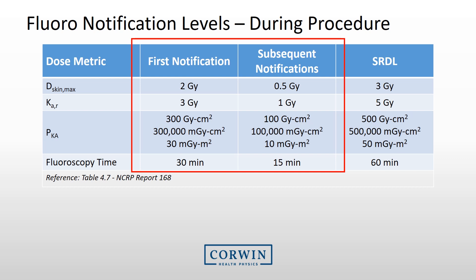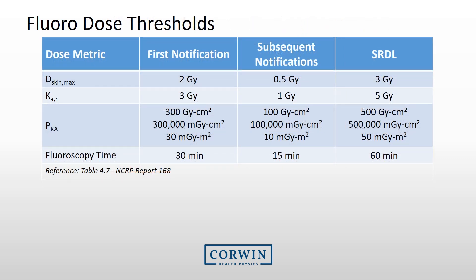Depending on your manufacturer, the reported units may differ. Similar to having recommended notification levels during a procedure, the Joint Commission requires facilities to have radiation exposure and skin dose thresholds. If these levels are exceeded, a further review and/or a patient evaluation is to be performed to check for adverse radiation effects, and the facility is also to review and analyze these instances.